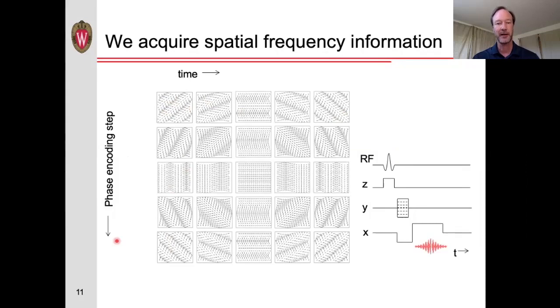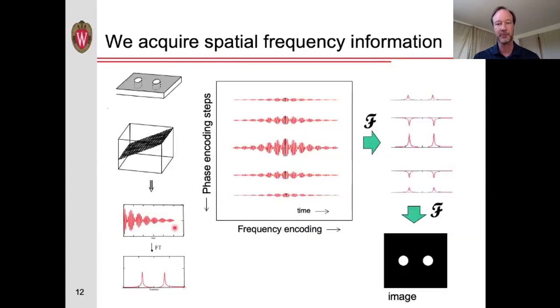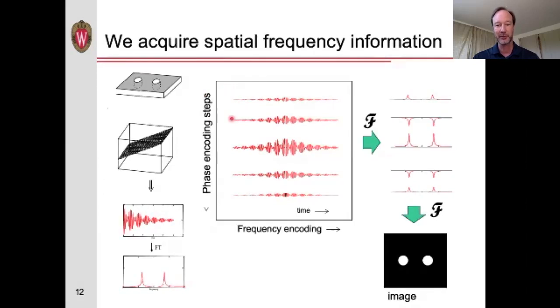I ended the lecture on MRI basics image formation with this figure here, showing how the magnetization vectors are twisted up by the frequency encoding along the x-axis, and by the different phase encoding steps along the y-axis. So putting this together, if we have multiple different phase encoding steps, if we look at the frequencies within each of these echoes, we can find out where the signal is coming from in the x-direction. And similarly, if we look at the frequencies across all the different phase encoding steps, we can find out where the signal is coming from in the y-direction.